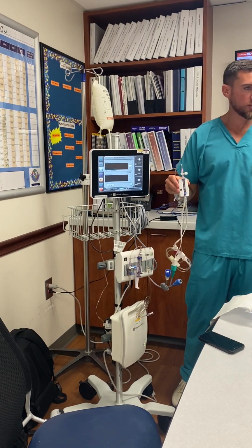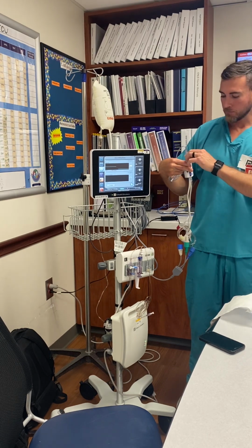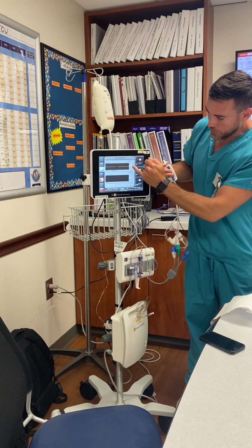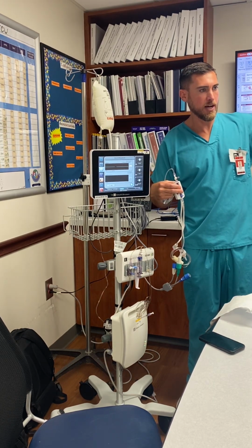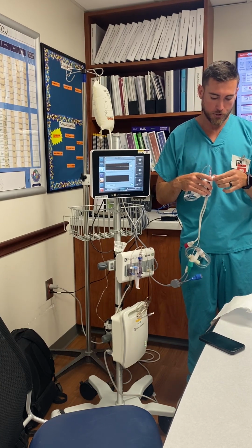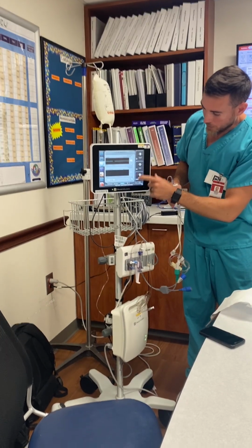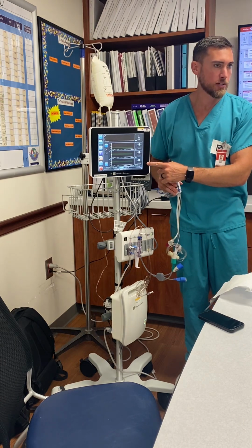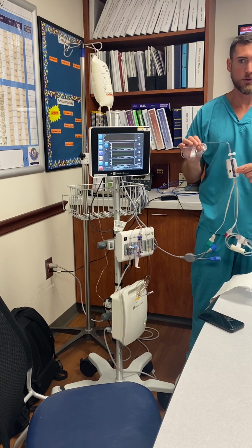And then you'd go through your zeroing process. So at phlebostatic axis, right, heart level, off to the patient, open to air, you'd hit 0 here. Go ahead and zero your bedside monitor at the same time. Come back here, close your stopcock, put your cap back on. You'll start to get your waveform, and then in 20 seconds, you'll get your continuous parameters. That's it. That's the beauty of a FloTrac.